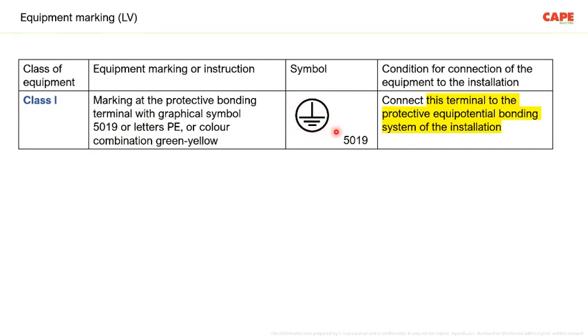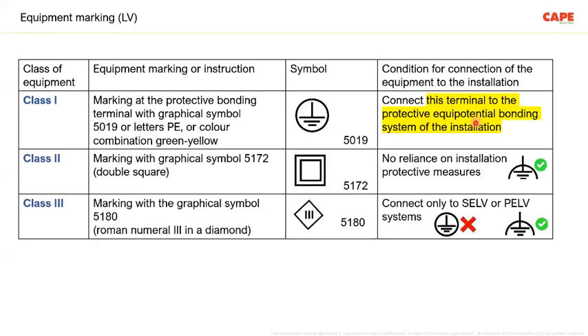And now, most important, what the consumer must do: once you buy a class 1 equipment and connect it to your building or installation, you must do protective earthing. What is protective earthing? Connect this terminal, the terminal of that class 1 equipment, to the protective equipotential bonding system of the installation. Then people will be trying to find out what exactly this protective equipotential bonding is. Let me skip these two parts.